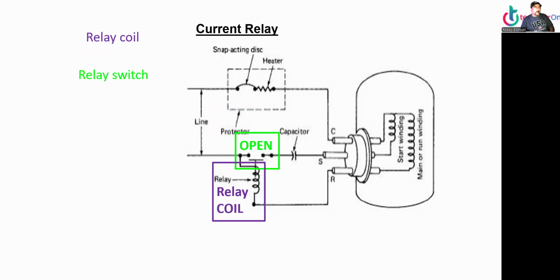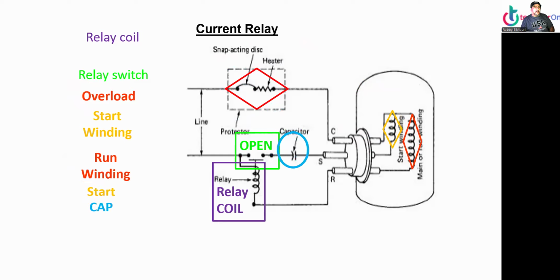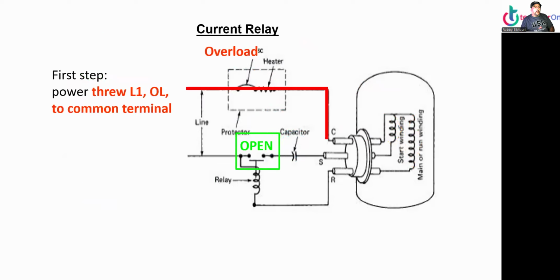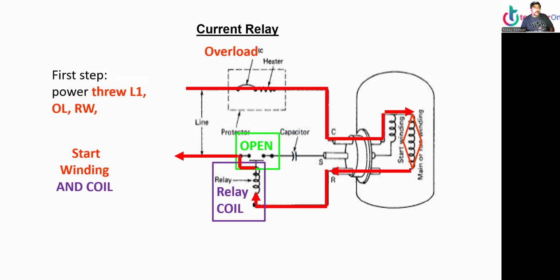Current relay switch open, overload, start winding, run winding, start capacitor should be all blue. First step: power goes from L1 to overload to the common windings and out through the start windings and the coil relay. This is one of the few times in HVAC where we have two loads in series, the coil relay and the compressor in series.